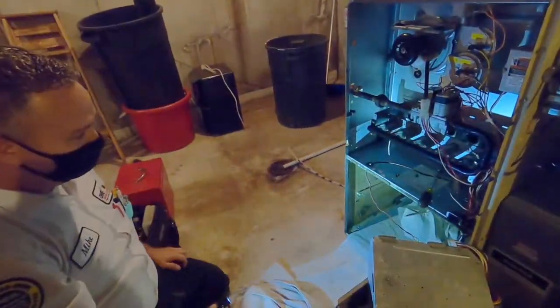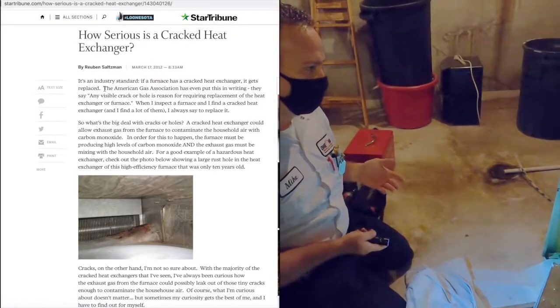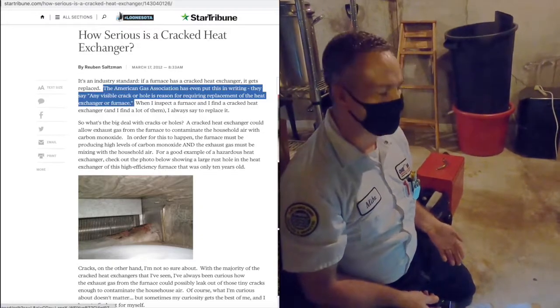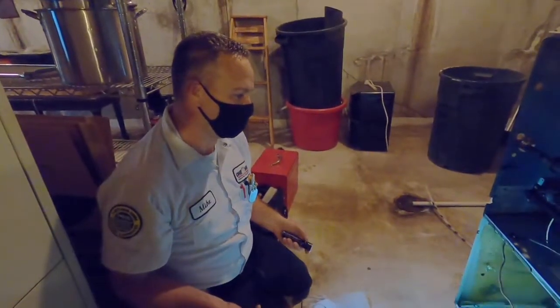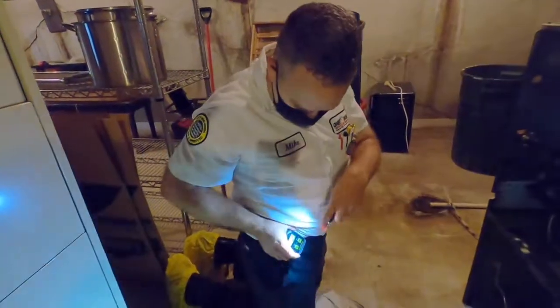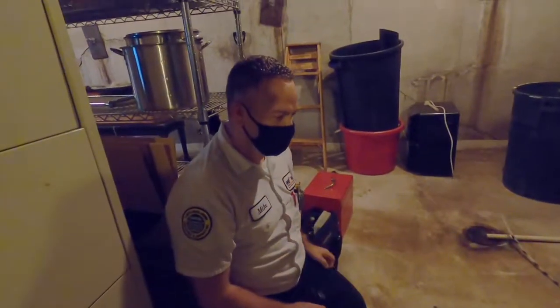The annual inspection ensures safety for the homeowner. Basically, if we find a crack or a flaw in the heat exchanger, the American Gas Association states that we either have to shut off the gas to the furnace until the heat exchanger itself is replaced or the furnace is replaced. We also wear a carbon monoxide detector on our waist in every home we go into.